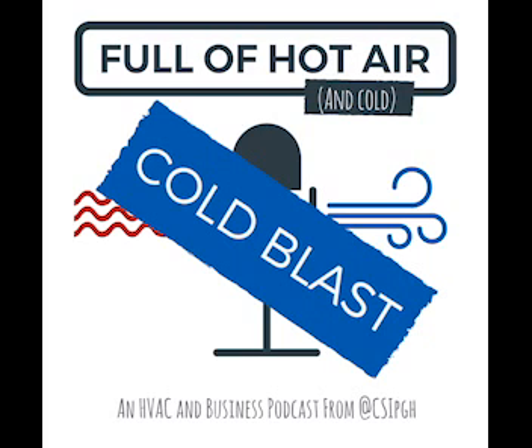Gotcha. And so where is the first step, just diving right into that indoor unit, or are we going to the outdoor unit? Where does that tech want to start? No, first I'm going to make them understand where this voltage comes from. First of all, the outdoor unit is what provides your high voltage and your low voltage communicating voltage. So the indoor unit is actually just receiving that.